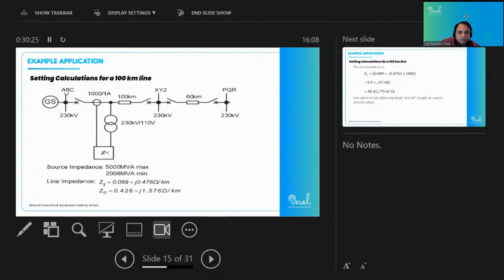Then Zone 2 will be from point ABC to the complete 100 kilometers plus 50% of the XYZ to PQR line. And this 50% will be a 30 kilometer section. So Zone 2 reach will be 100 kilometers plus 30 kilometers, so a total of 130 kilometers we will be protecting through Zone 2. And for Zone 3, there are different approaches. We need to check whether there are multiple lines. In this typical case we are taking only one line, but if there are multiple lines from this XYZ terminal bus bar, then we need to consider another approach. But for this typical case we are taking this one.